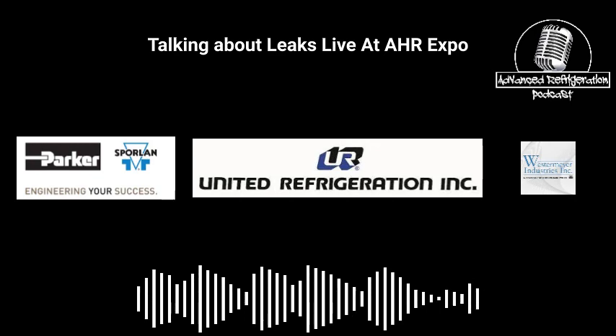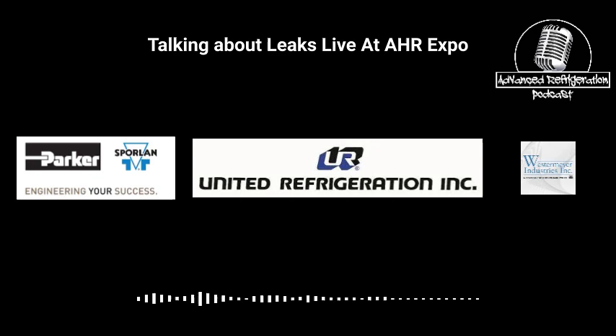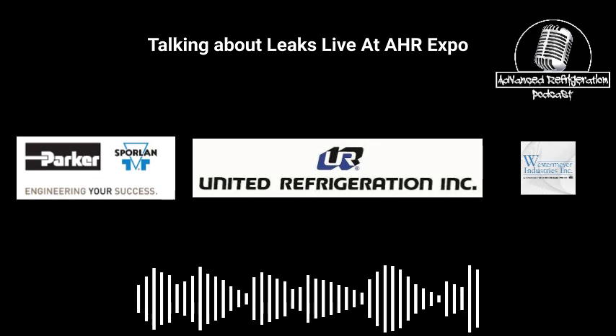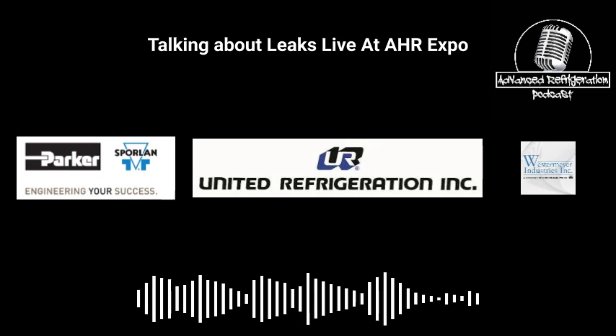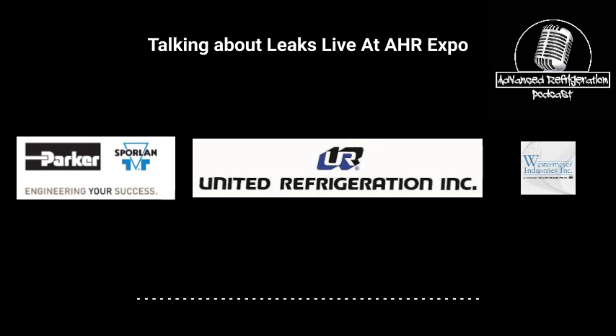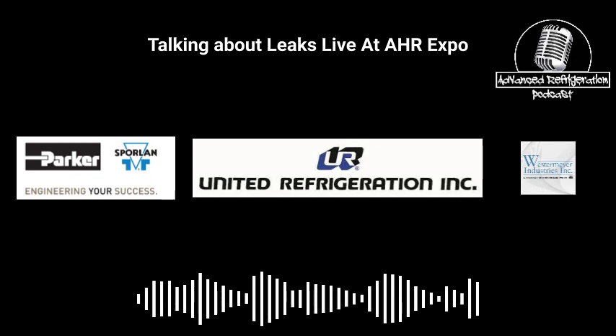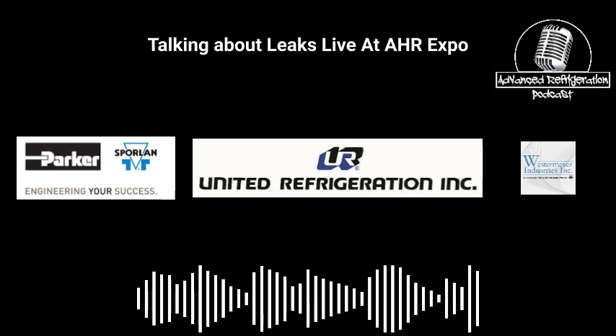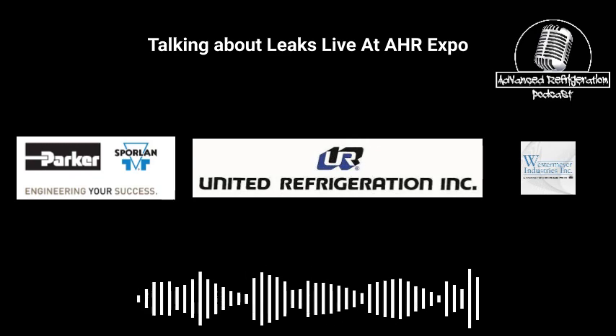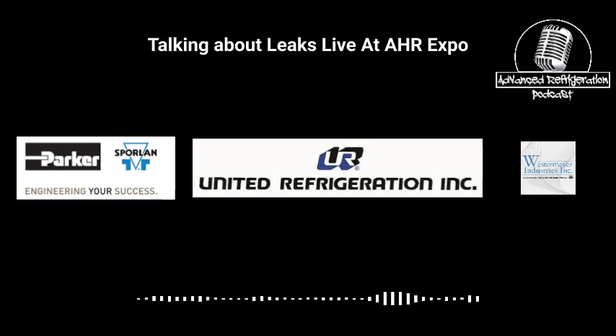Yeah. So typically what Kevin's stating is basically there's a certain frequency where those compressor bearings just don't like. So a lot of times, like you said, with most VFDs you can basically go through the parameters and skip that out. So if it's flipping out at like 47 hertz, skip that and turn it up, because you have compressors that say they can go all the way up to what? 87 hertz? I refuse to bring them that high because they sound like they're going to come apart. They say that you can though. Yeah, but then when it fails, it's always liquid flood back.